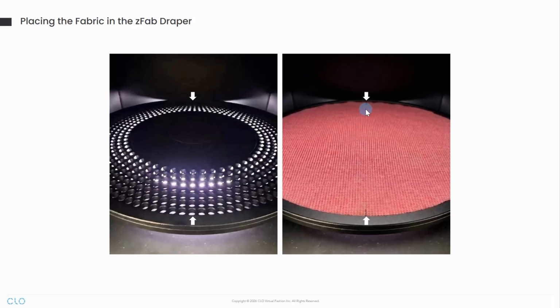If the size of the fabric sample doesn't match the Draper guard, an error may have occurred during the cutting process. Therefore, you will need to double check that the sample was cut to exactly the 30 cm diameter specification.